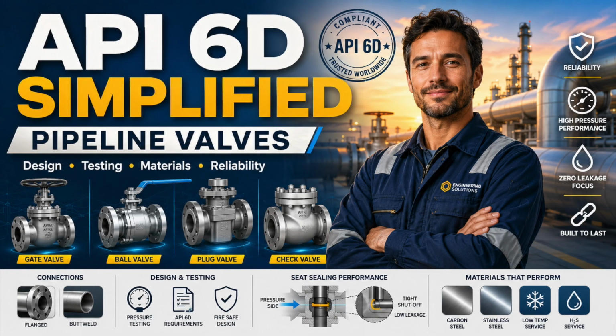Low-temperature service needs the same discipline. Do not stop at specifying a low-temperature body material. You need impact toughness for pressure-containing parts. You may need weld metal and heat-affected zone impact testing. You need compatible bolting. You need seals that remain functional.